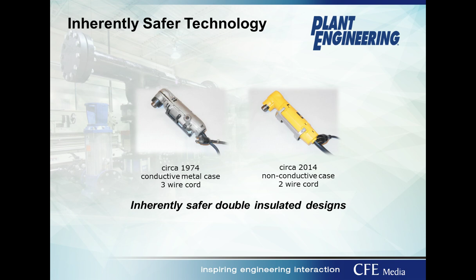This one was purchased in 1974. It has a conductive metal case and a 3-wire cord. Now, if the 3-wire cord is plugged into a 3-wire outlet and everything is intact, there's no broken equipment ground, the 3-wire outlet has been installed properly, and you have a failure in the insulation inside the tool, then the case will be grounded, and so you're not exposed to electrical energy. However, if you have a failure in the cord, if the equipment ground is broken, if the third prong is broken off, if it's plugged into an extension cord that has a defective equipment ground, either a broken wire or a broken off prong, then that safety feature does not exist, and you could be exposed to a serious electrical shock incident. So the newer non-conductive double insulated tool on the right-hand side, the yellow one, is an example of the continuing evolution in inherently safer technology.